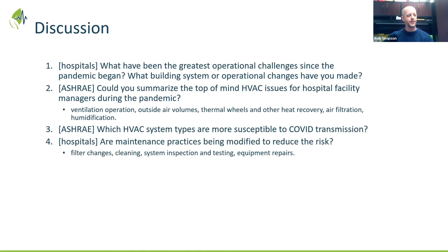I wanted to go back to what you said about the lack of concern with airborne particulates going through an HVAC system and being spit out through the supply. I think we all agree it's very low risk right now, but I'm curious what about areas with open air plenums? Some of our clinical spaces were once administrative areas retrofitted to clinical space, and may not have ducted air or a return air system. So that's a common question I get: what risk does that open air plenum pose, where right above the ceiling air can be mixed and shot back into the occupied space, clinical or non-clinical?